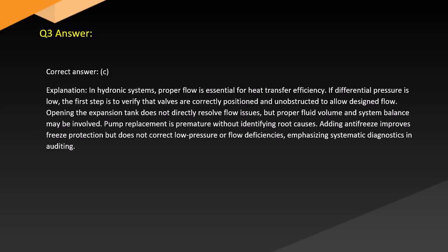Answer. Correct answer: C. Explanation. In hydronic systems, proper flow is essential for heat transfer efficiency. If differential pressure is low, the first step is to verify that valves are correctly positioned and unobstructed to allow designed flow. Opening the expansion tank does not directly resolve flow issues, but proper fluid volume and system balance may be involved. Pump replacement is premature without identifying root causes. Adding antifreeze improves freeze protection but does not correct low pressure or flow deficiencies, emphasizing systematic diagnostics in auditing.